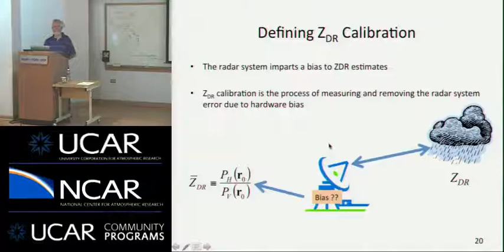How accurately do we have to do it? Well, there are numerous papers over the years where the general consensus of the research community is that you need to be able to measure ZDR to an accuracy of 1/10 of a dB or better. And there's a good illustration of that in the Bringi and Chandrasekar text, figure 8.8, where these contour lines are the errors in your rainfall rate estimates, where you were using reflectivity and differential reflectivity as your input parameters. And this box here, where I've drawn, shows our current requirement, which is to maintain reflectivity within plus or minus 1 dB and ZDR within plus or minus 1/10. And you'll see that down here, where you have an error of +1 in Z and -0.1 in the ZDR, you can have a 30% error in your rain rate estimate.